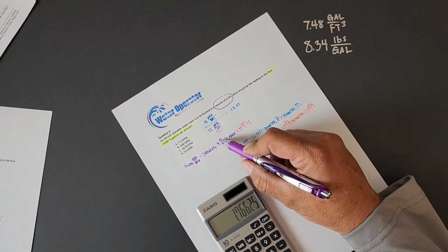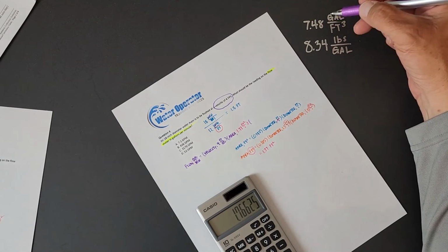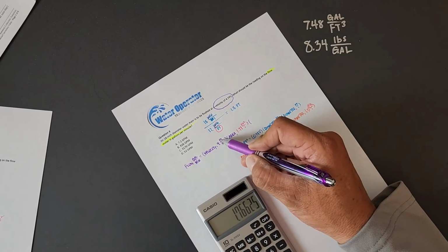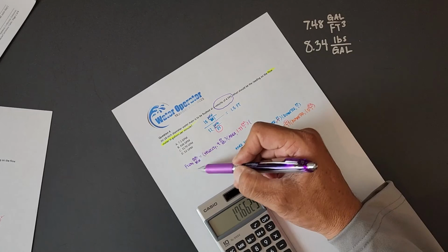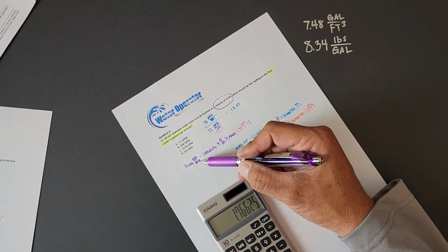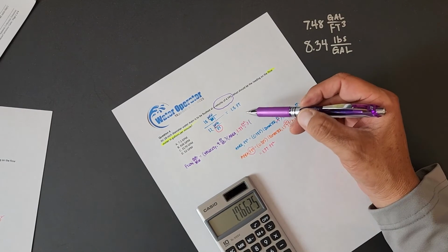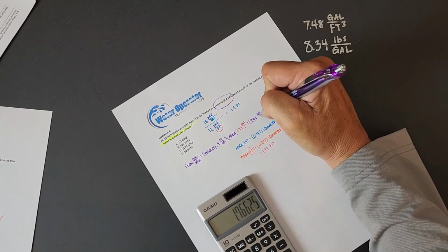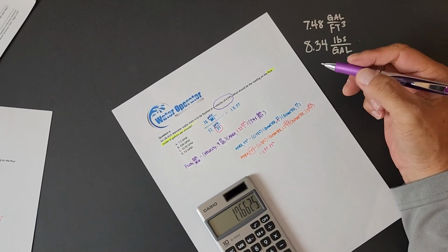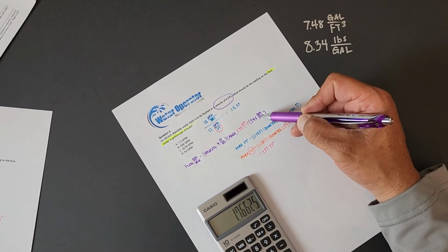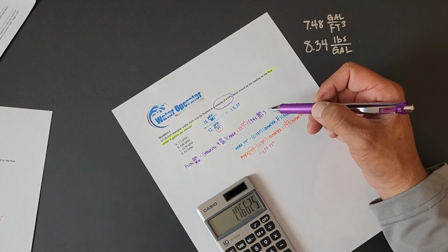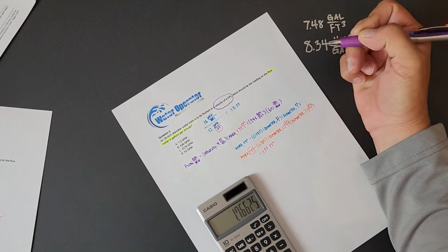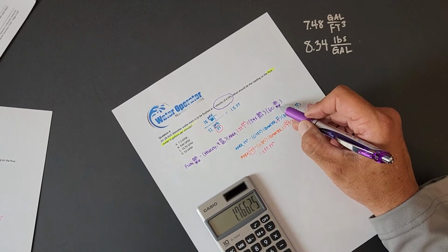So now we have foot, square foot. We have this conversion factor, 7.48 gallons per cubic foot. This helps me out a lot because cubic foot is below the division line, I can eliminate this foot and this foot. I'm doing that because there is no footage unit of measure in the answer. It's in gallons per minute. So I'm eliminating the footage, but I also need gallons. So that 7.48 gallons per cubic foot is helping me in a couple of ways. Eliminate this foot, eliminate that foot, cross cancel out here. But it also leaves in gallons. Now I need to convert seconds to minutes, so 60 seconds per minute. Now I can cross cancel out the seconds and I'm left with minutes.